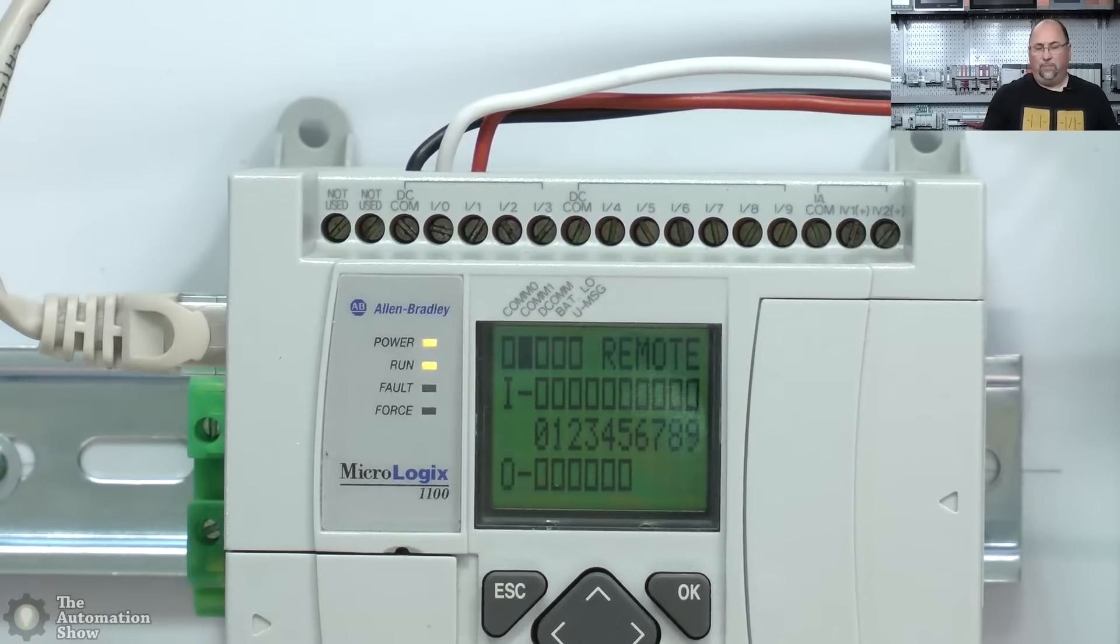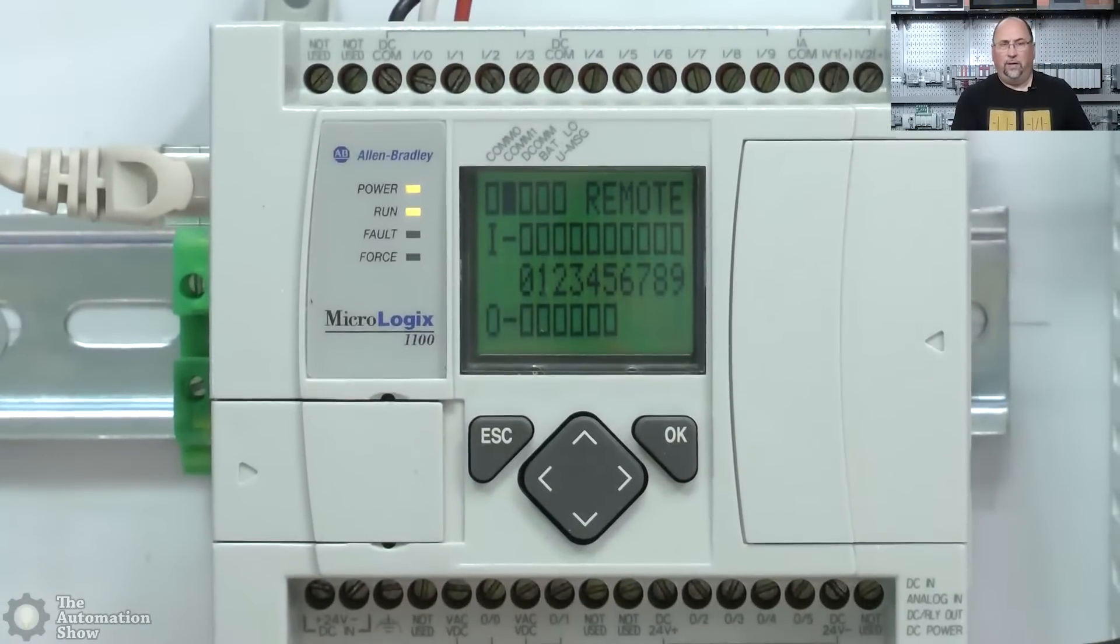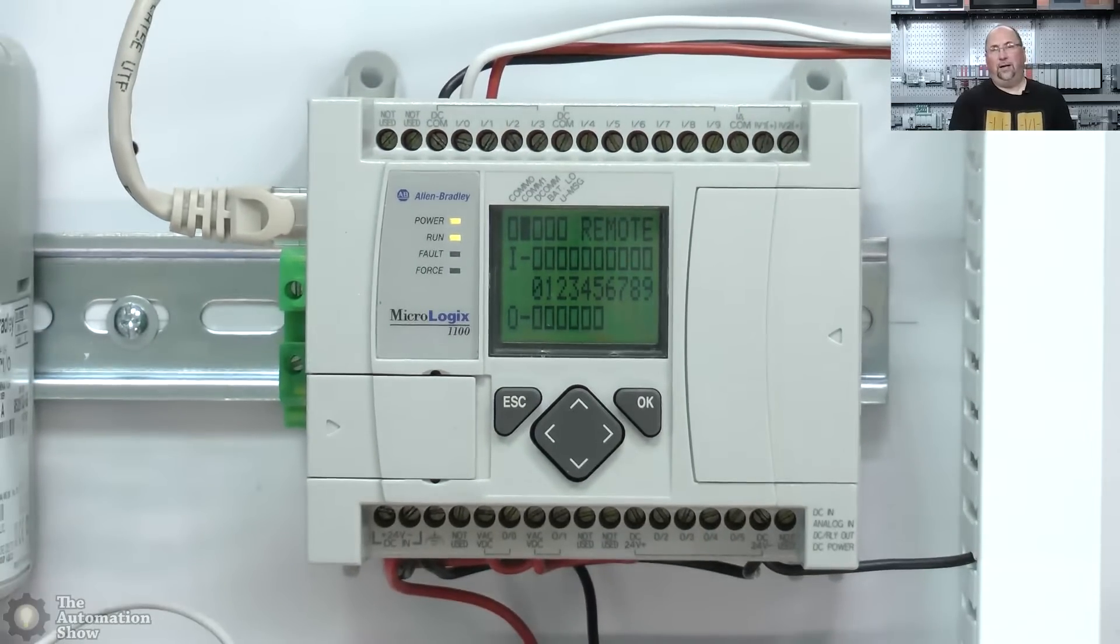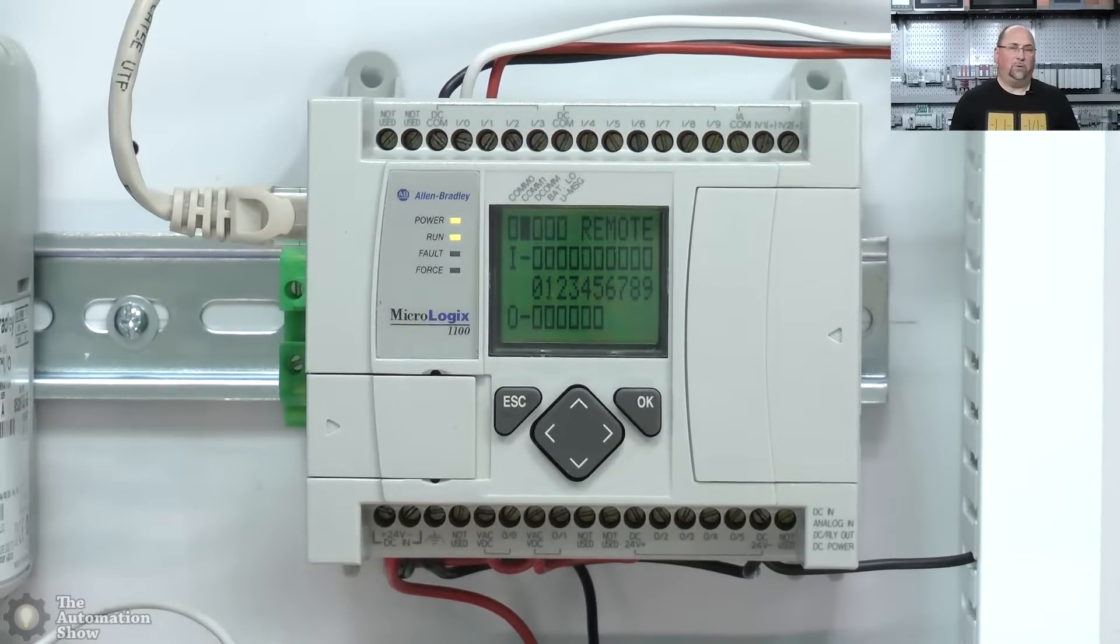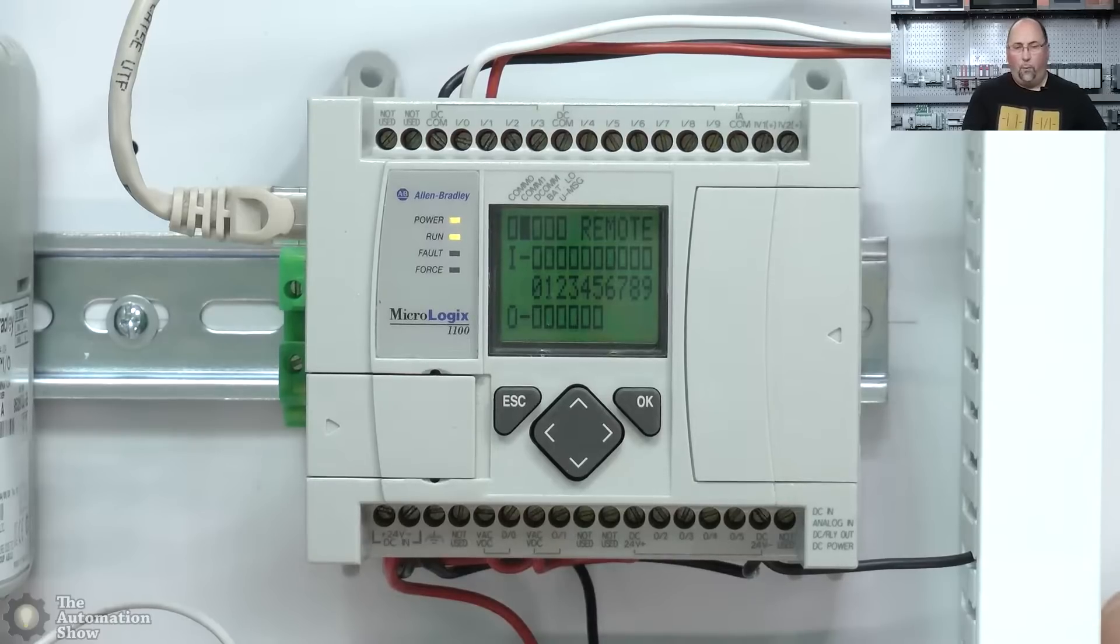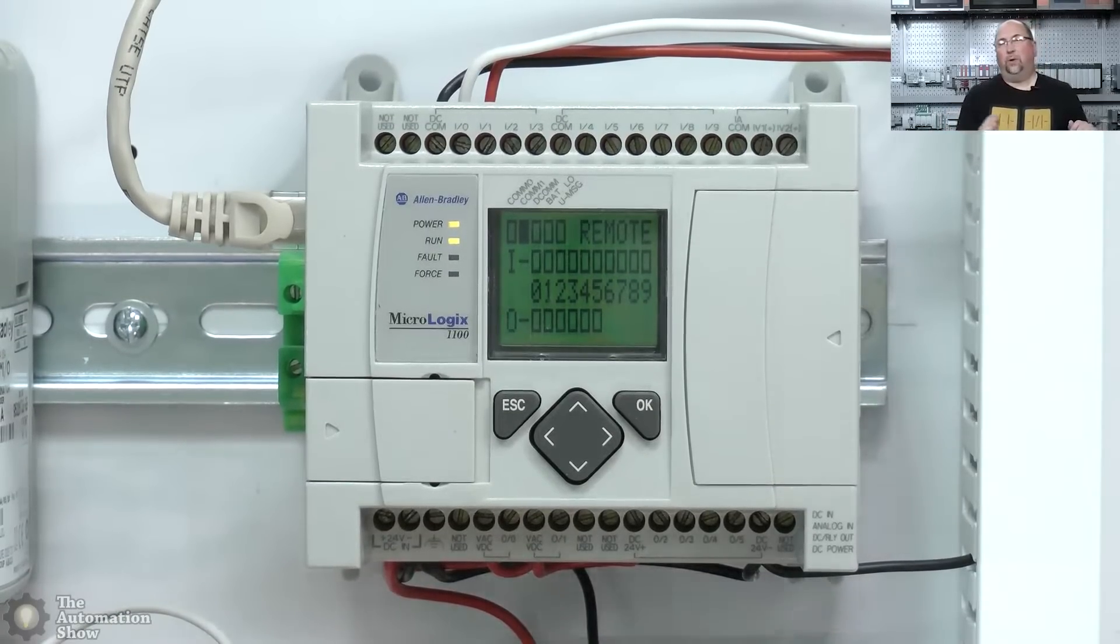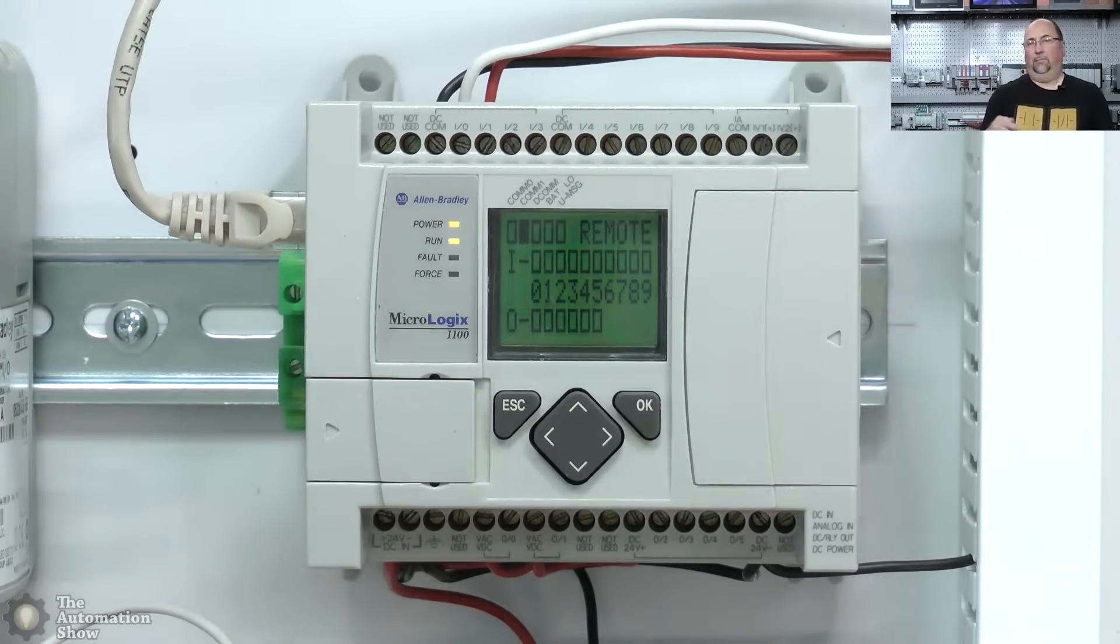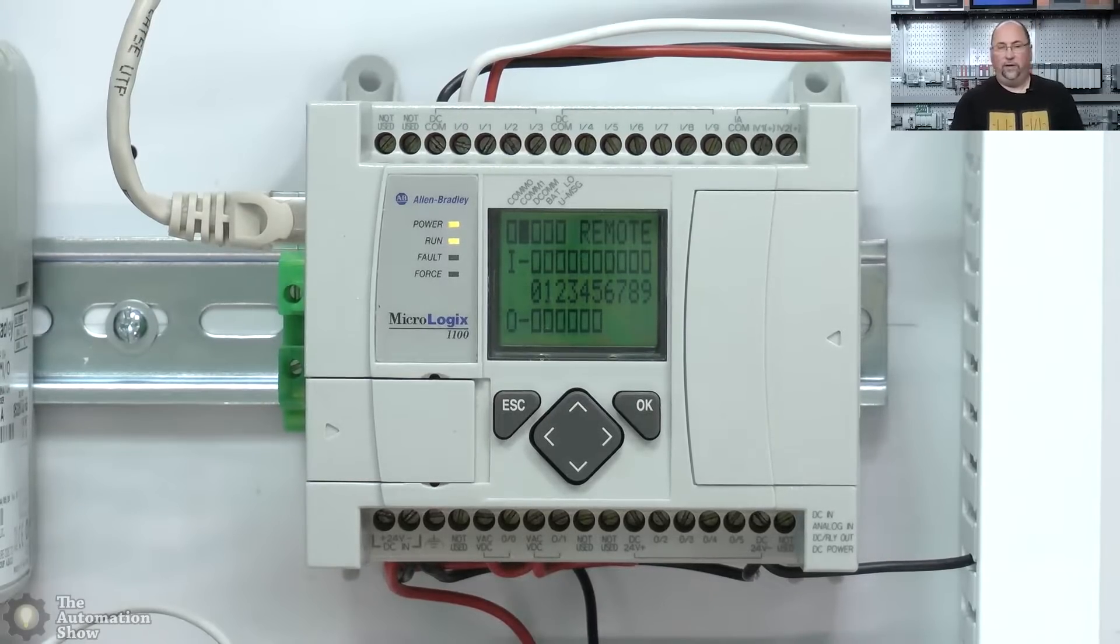So there you can see I got the white or A going to zero and I have the red B going to one. And that's because the MicroLogix 1100 supports four high-speed DC inputs. Now I have a series A, so they only go up to 20 kilohertz.